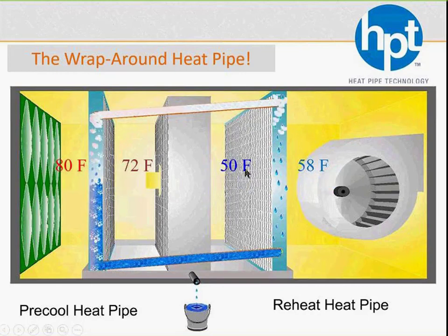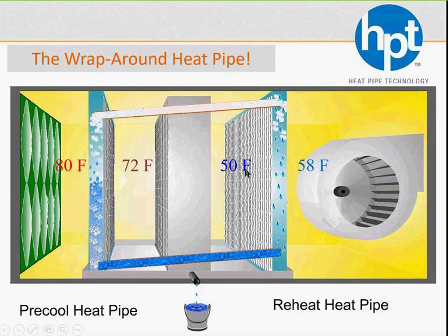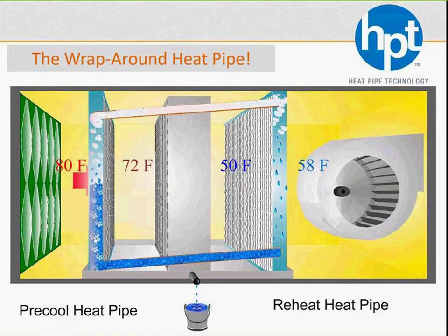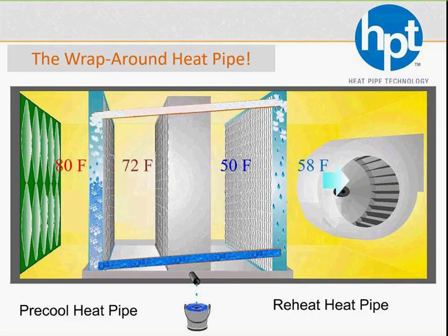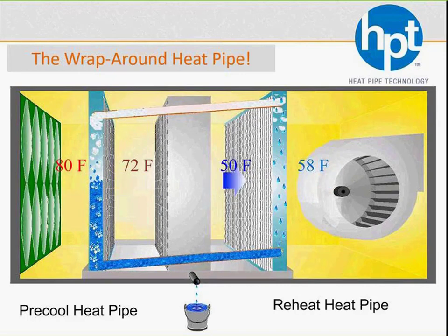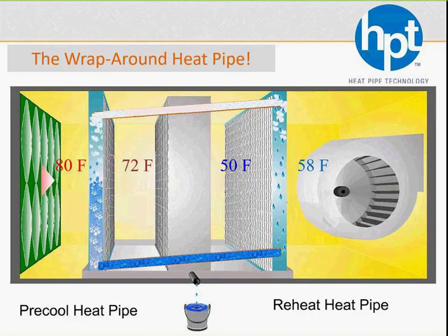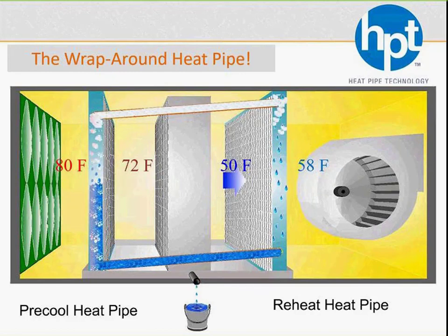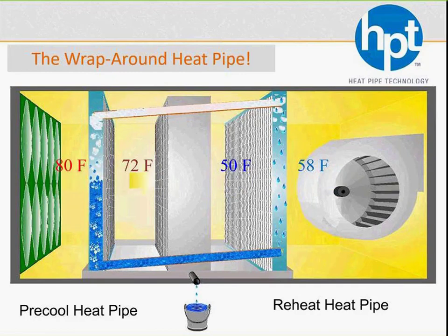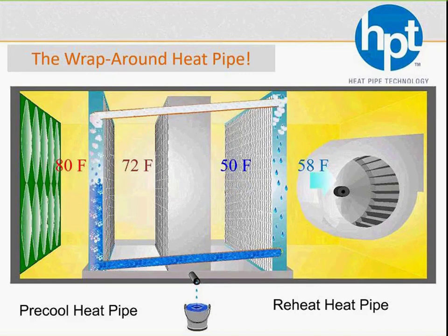And the advantage of the reheat, obviously the biggest impact, is going to be energy savings. Even when you use gas or hot water, depending on the location, there can be significant energy costs with that. I've seen instances where we completely replace gas or hot water reheat, and I've also seen scenarios where we do the majority of the work in certain climates, or hours during the year where we don't do enough to reheat. Well then, any additional reheat downstream can do the rest of the work, but there's still energy savings there. And that's the biggest effect of the reheat.